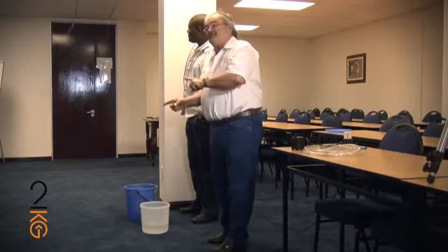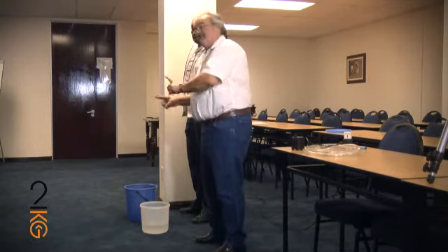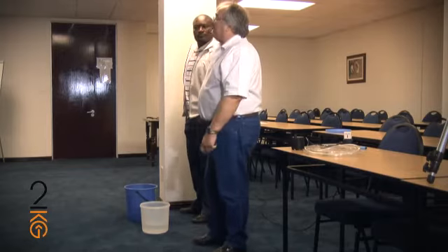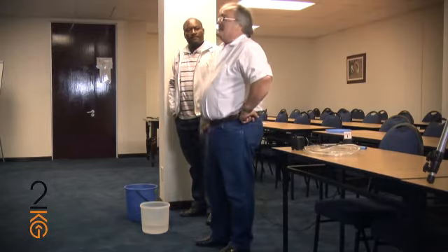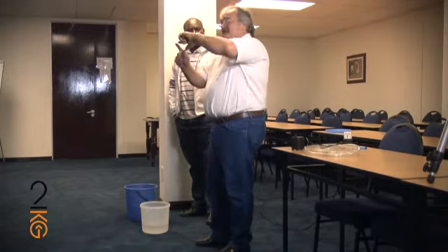But the system drags the pump all over the curve. And people have said to me, well, if the pump is properly designed into its system, you don't have to mess with the valves. Wrong. The design engineer draws a triangle on a curve and says, this pump is operating here on the curve. Wrong. Pumps are operating all over the curve. The idea is to control them.